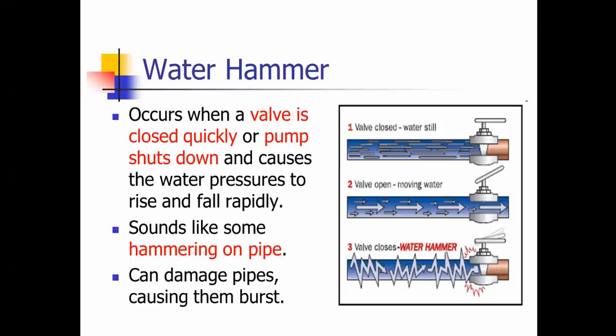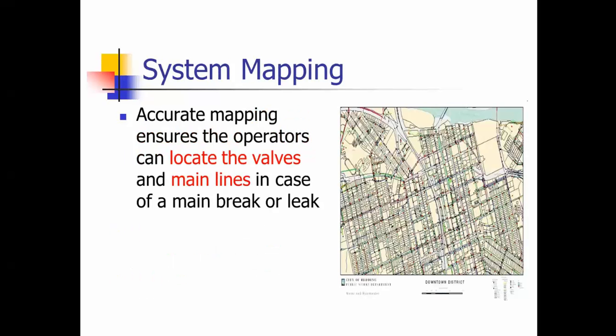Water hammer occurs when the valve is closed quickly, such as in a check valve, or you can close a gate valve too quickly. One thing that I was taught when I was an operator is that you can't close a valve too slowly, but you can close a valve too quickly. So make sure that when you close a valve, you do it very slowly, because the rapid pressures back and forth cause that water hammer, and it can cause a rupture in a line. Your system mapping should be accurate, and it should ensure that the operators can locate the valves when you have a mainline break or you need to shut something down.